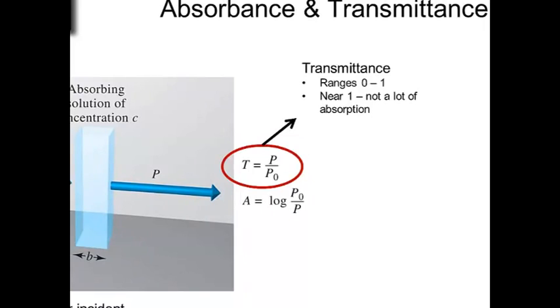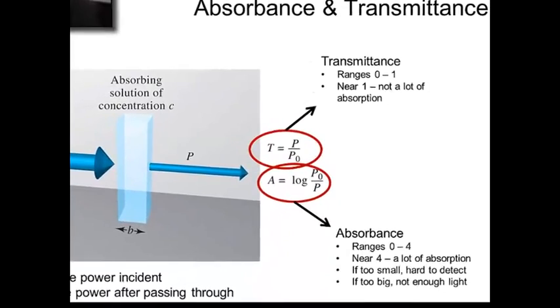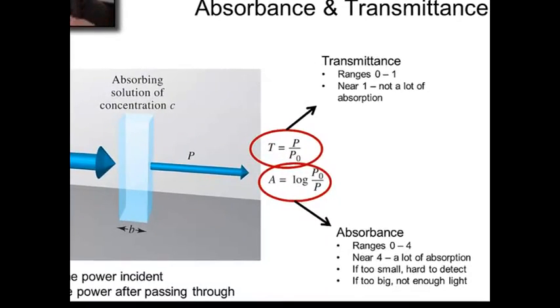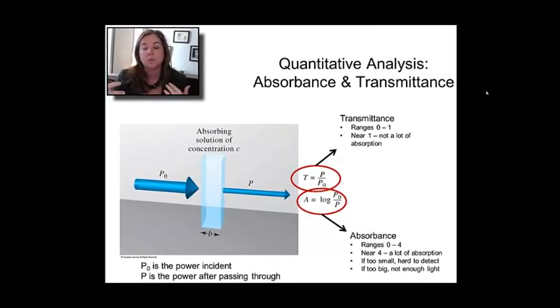Transmittance will range from 0 to 1, and near 1 there's not a lot of absorption. Absorbances will range 0 to 4, but you don't want to operate in that big of range because at 4, very few photons are getting through your sample. It's too black. The optimal is about 0.3 to 0.8 in terms of absorbance because you take enough photons out, but not so many that you have to resort to photon counting.